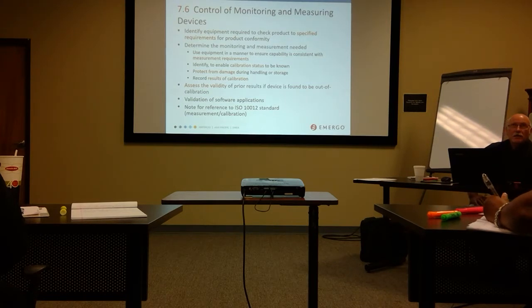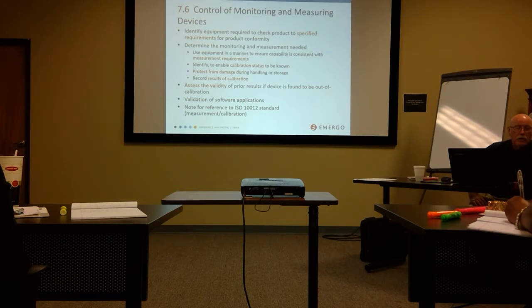The status of that instrument should be noted on the instrument itself. I should be able to go pick up that set of calipers, turn it over, and see the calibration tag on it. It identifies that and tells me when it was calibrated and when it's due next. Failure to have any of those components is a non-conformance. You will be cited. Questions? This is more important than a lot of people think about.